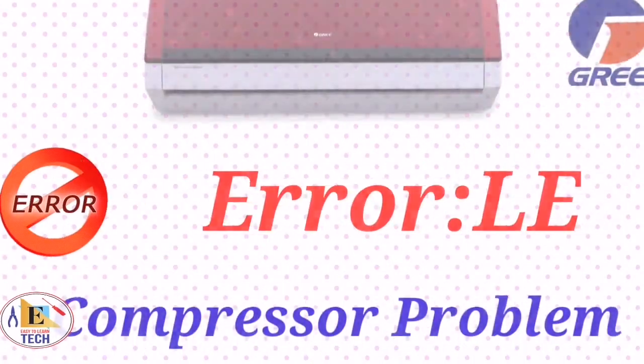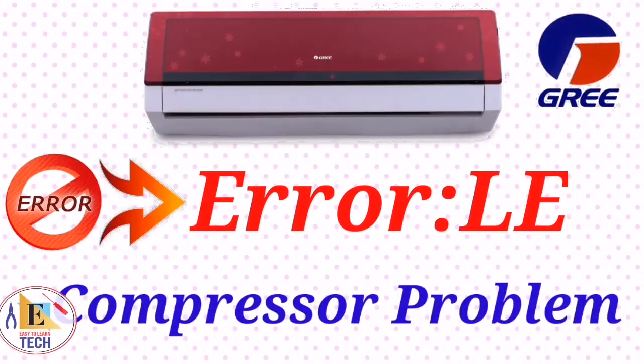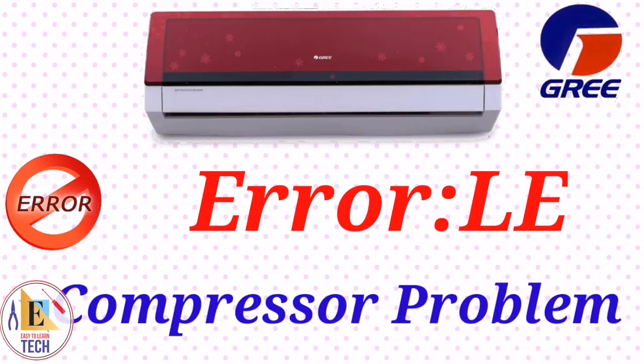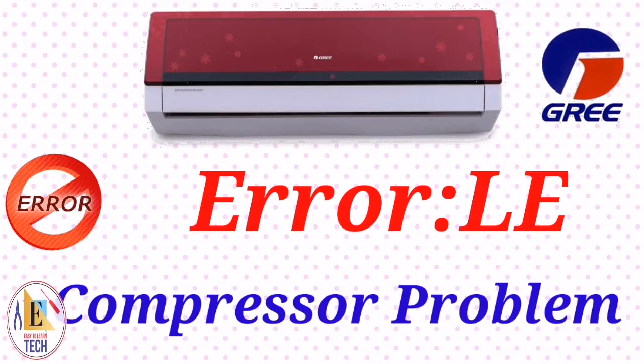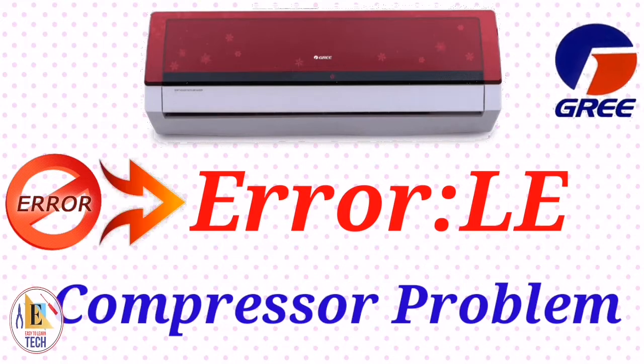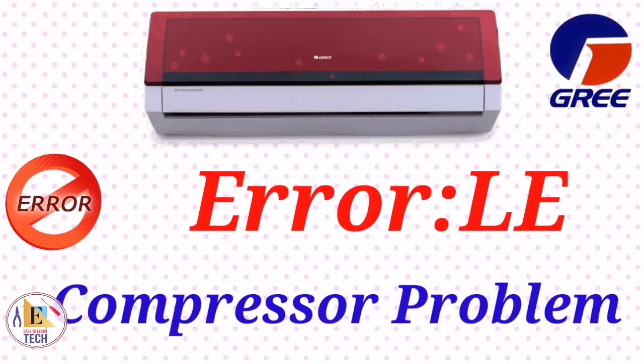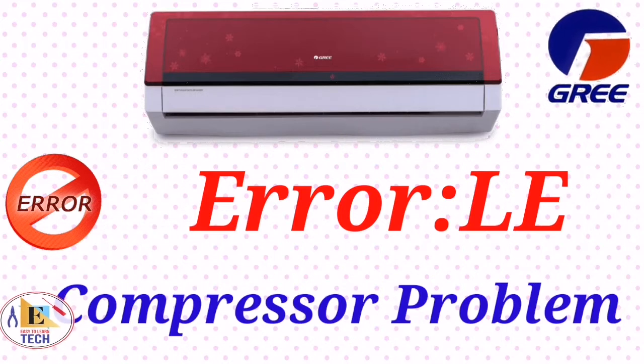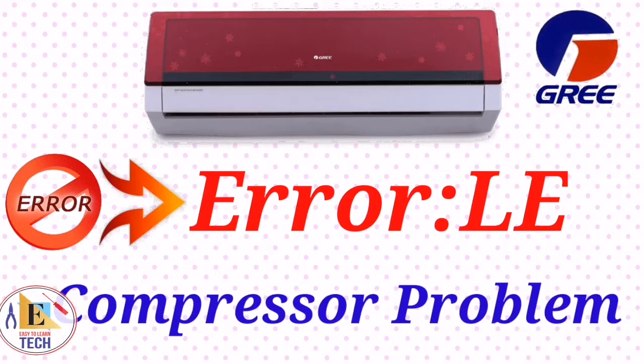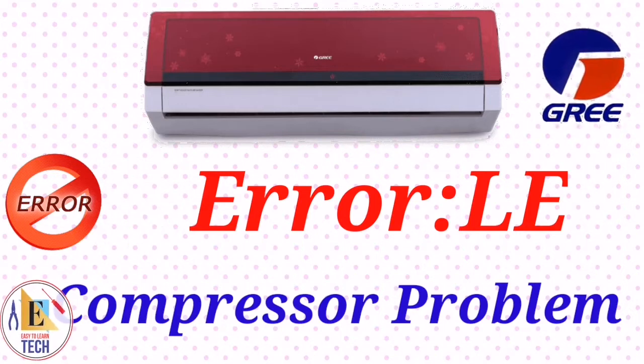Let's see the next error code. When you see LE in your display, it means compressor problem. Without checking anything, directly come to the compressor, check the wiring of your compressor terminal, then check the wiring in your outdoor PCB, if it is well connected on both sides or not. If it is not connected properly, connect it properly and start the unit.